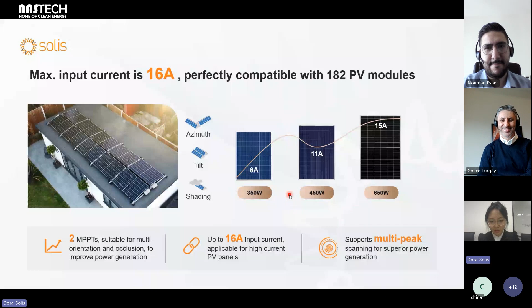The max usable PV input power can reach 1.6 times, so it's better than the competitors. For example, if the customer installed the 8 kilowatt hybrid inverter, the max usable PV power is 12.8 kilowatt. The inverter can supply the 8 kilowatt power to the load, and the excess 4.8 kilowatt PV power will charge the battery at the same time.